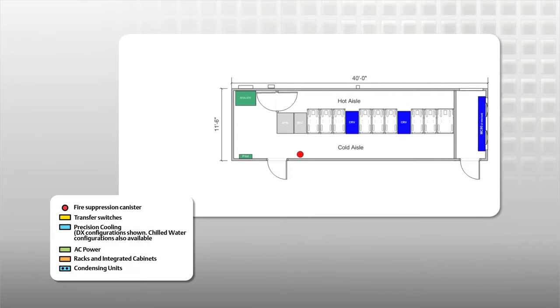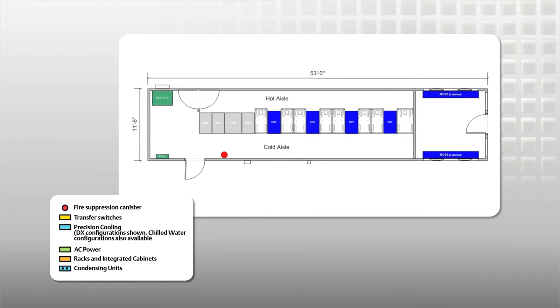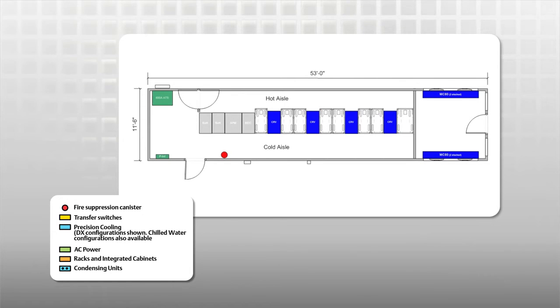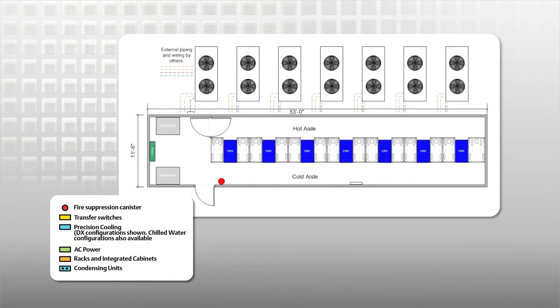The first supports 30 kW of equipment load with N+1 power and cooling. The second supports 75 kW with N+1 redundancy, or 90 kW with N power and N+1 cooling. A third option splits the IT and power enclosures for increased modularity.